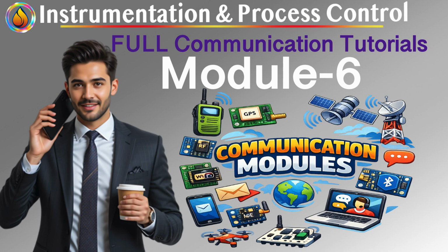Bit-oriented networks, when reality is binary. Bit buses live at the very edge of automation. They deal with presence, absence, on-off, true, false, nothing more. Typical devices here are proximity switches, limit switches, push buttons, simple pneumatic actuators. These networks move bits, not values. The data answers questions like, is the sensor active? Has the switch closed? Is the actuator energized? No scaling, no diagnostics, no nuance, because none is needed.